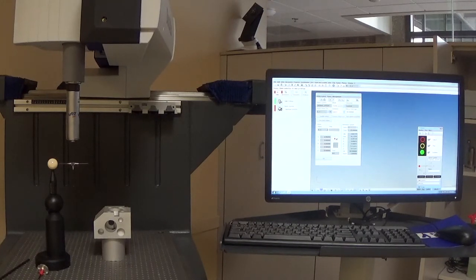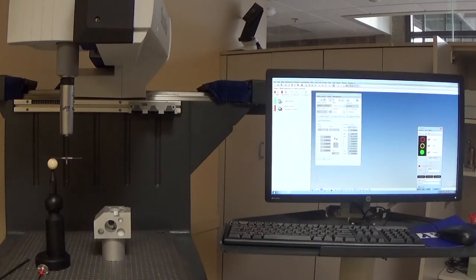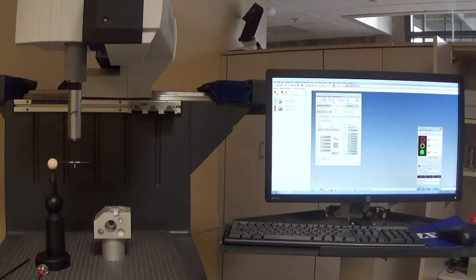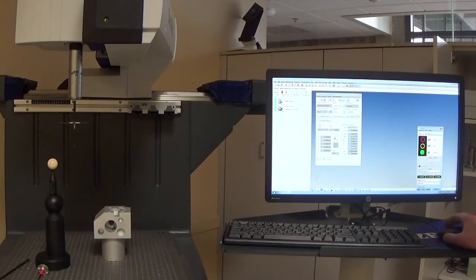Now our stylus qualification of tip number 5 is almost done. It goes through this last sequence where it measures the sphere and calculates the diameter of the stylus ball. And we're done. We get the green check mark and our number is 22 millionths, less than 30 millionths, so we're good. So now we're all done with the stylus system construction and this qualifying of all the stylus. So now we can start measuring.